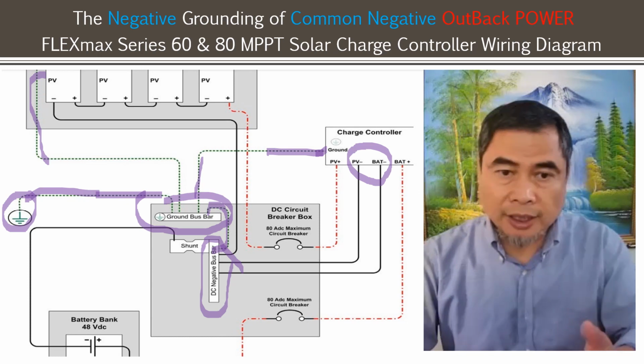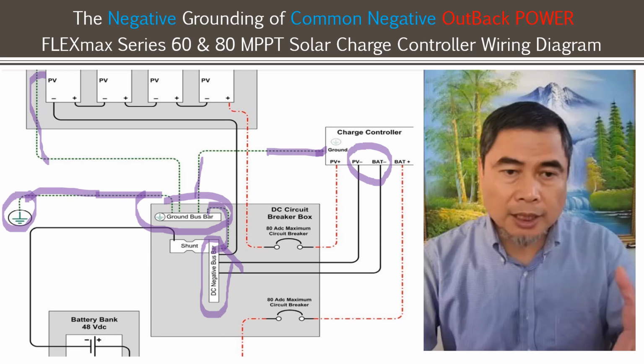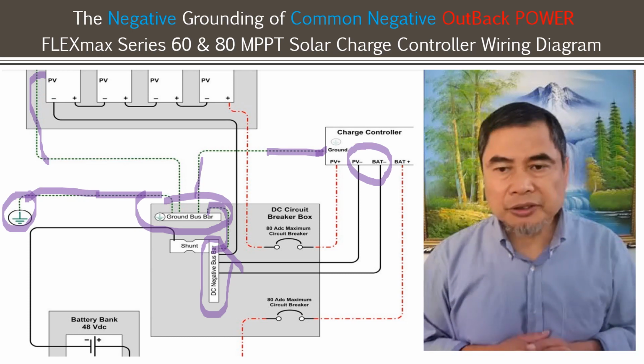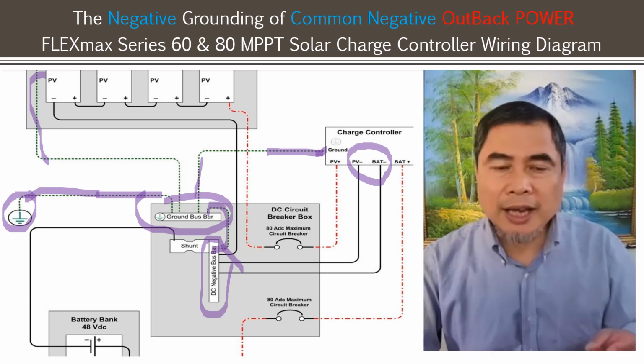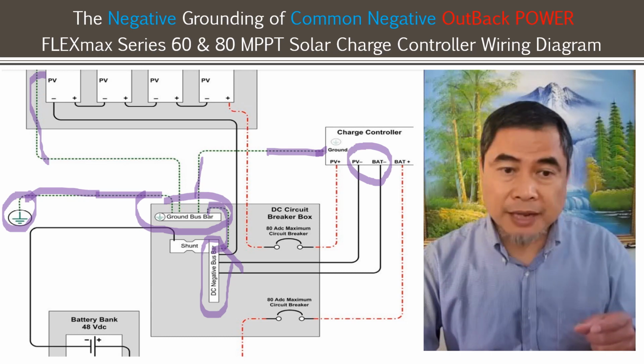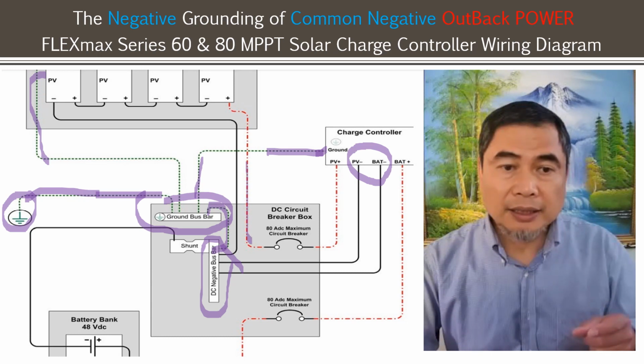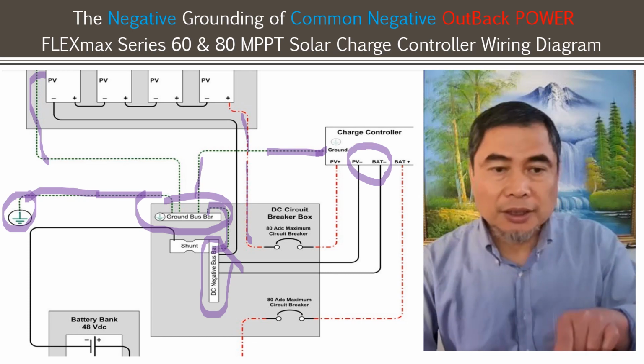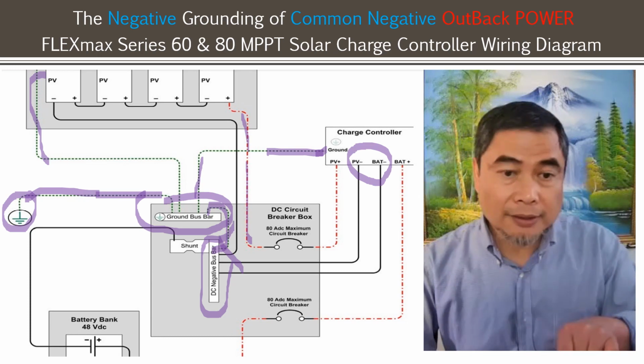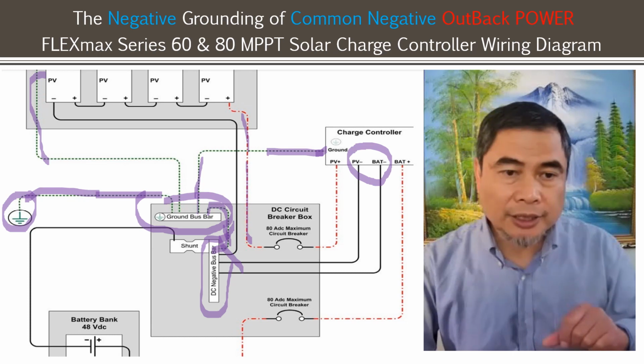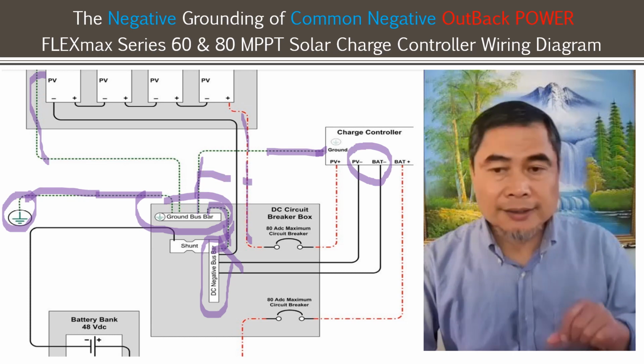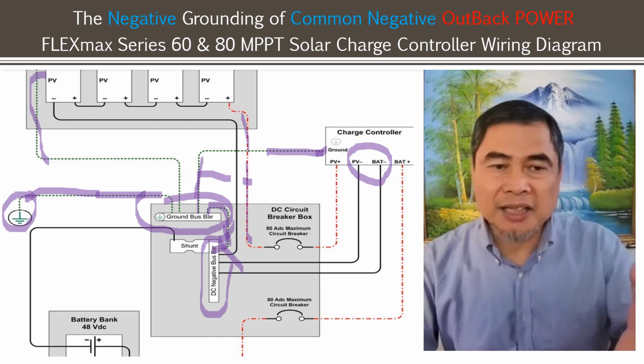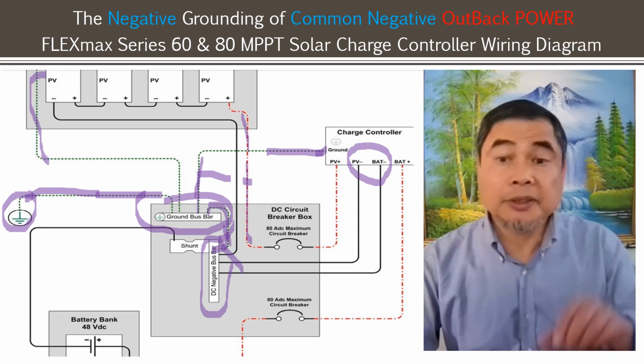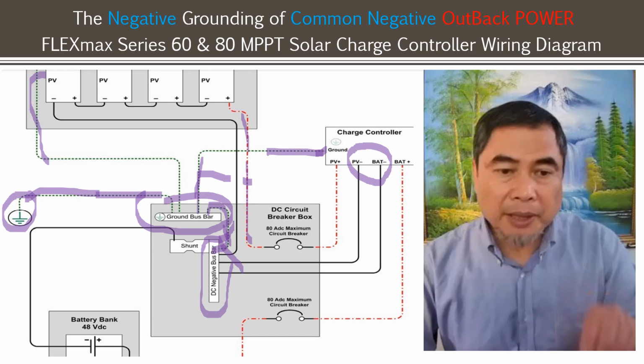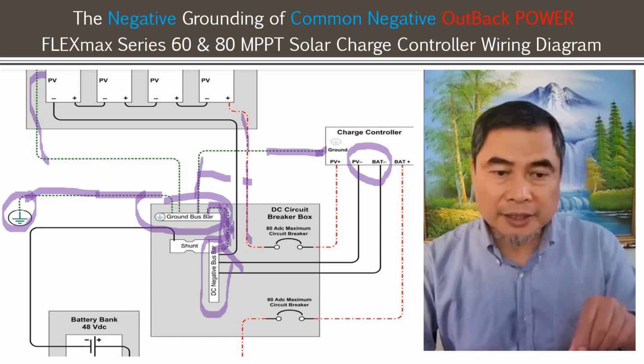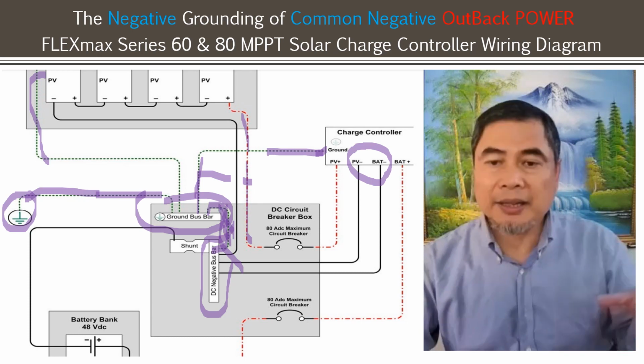Based on the design, this is one of the recommended applications, but some applications may ask to have PV positively grounded. But you could just disconnect this ground and then connect this one to the positive. And some of the electrical code may ask for PV positive to be grounded. It can be, but you have to make sure this PV negative is disconnected. You can't have both grounded.